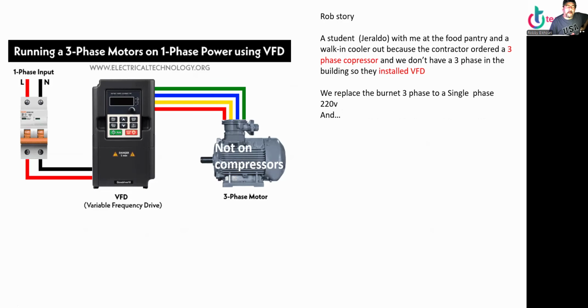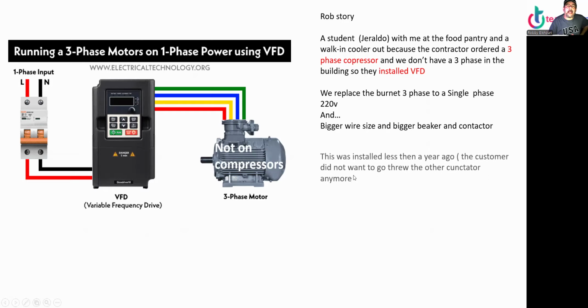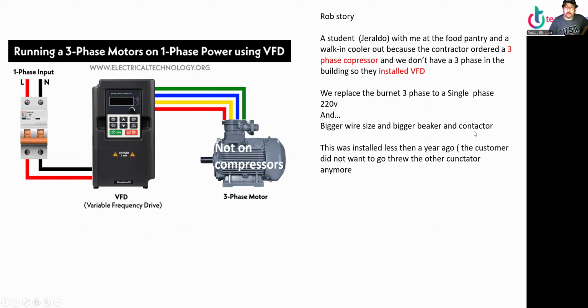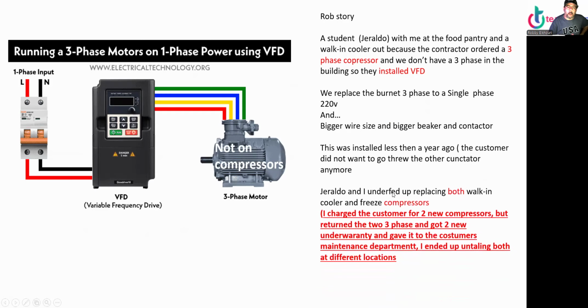So the 3-phase, it adds one more phase for the 3-phase. It's fine for the motors, but it doesn't work for the compressors. So we replaced the burned 3-phase with a single-phase 220-volt and bigger size wire, bigger breaker, and contactor. This was installed less than a year ago. The customer did not want to go through the other contractor anymore.